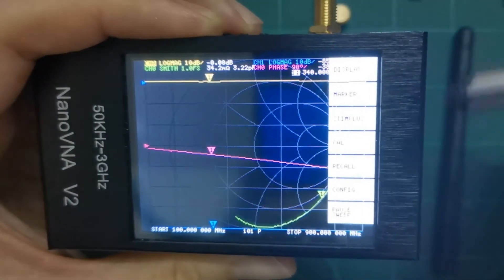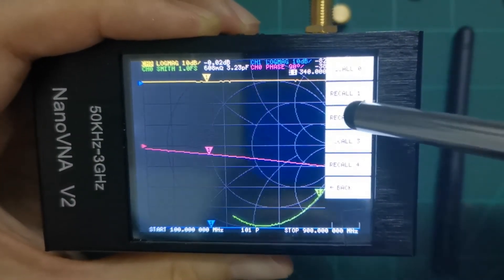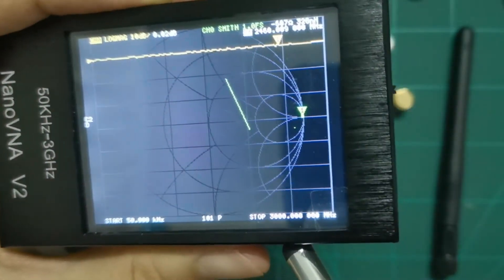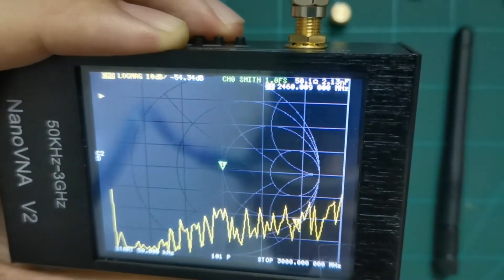Now we do a recall of state number two — the one we saved. You can see it restores to 50 kilohertz until 3000 megahertz, including our calibration. Attaching the load shows the same calibrated result.